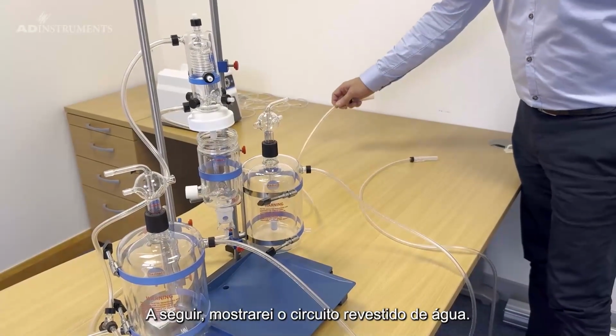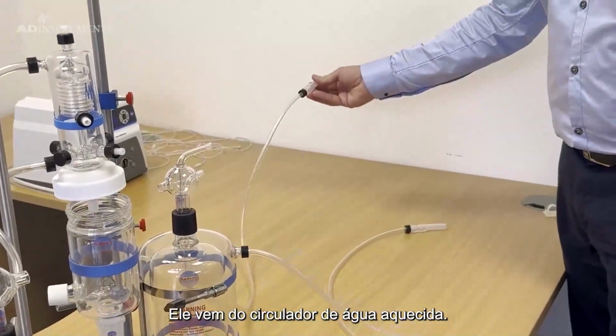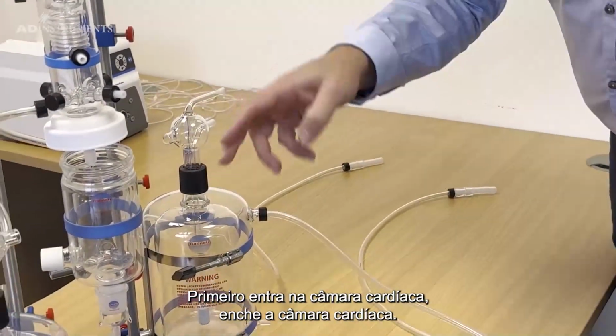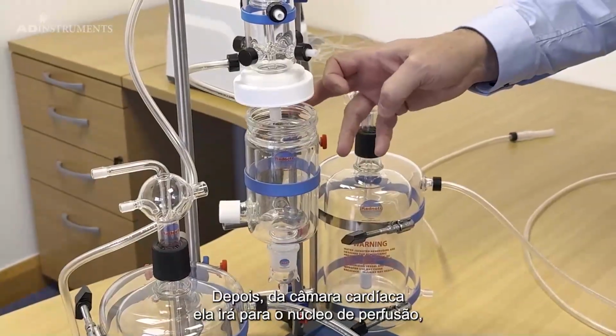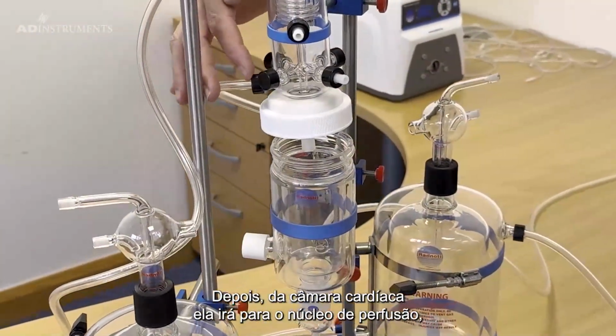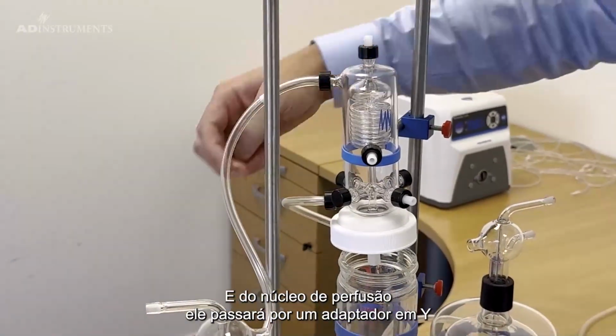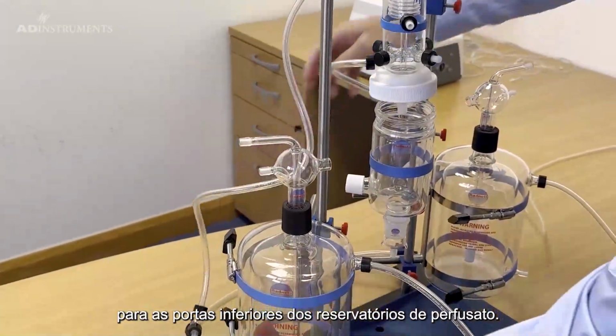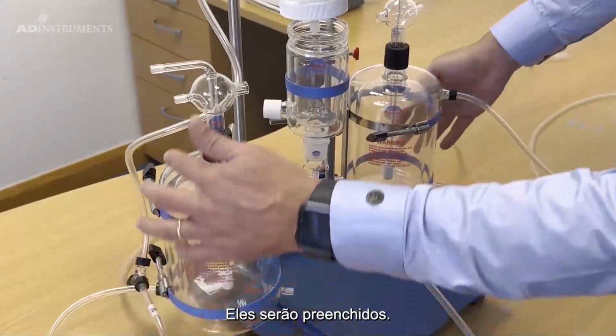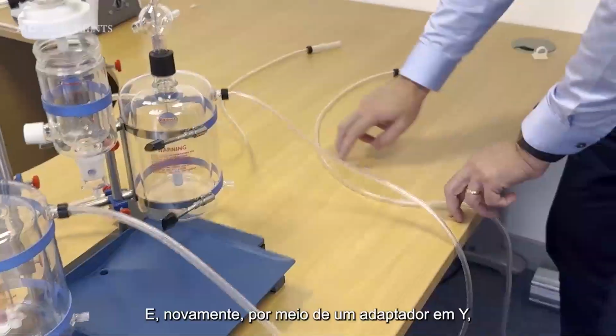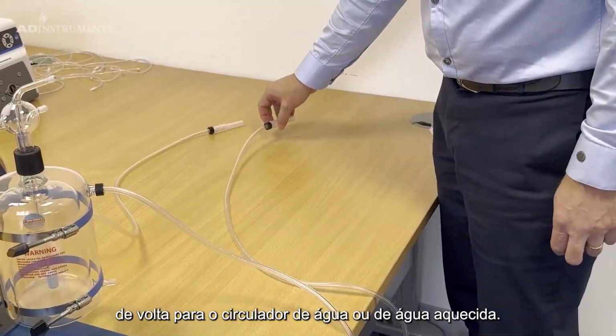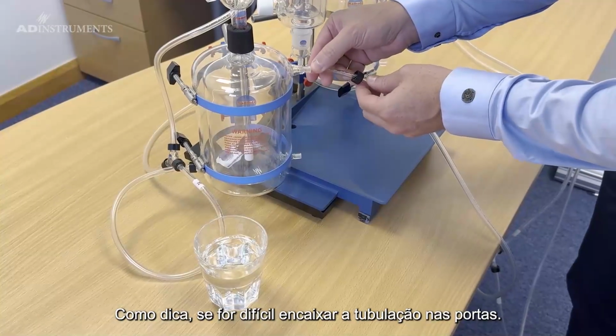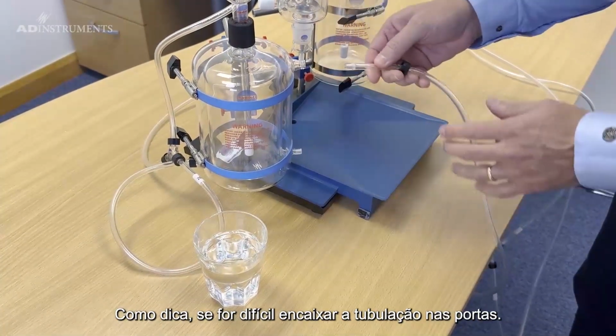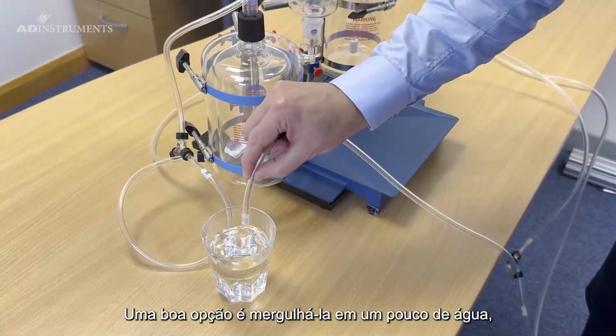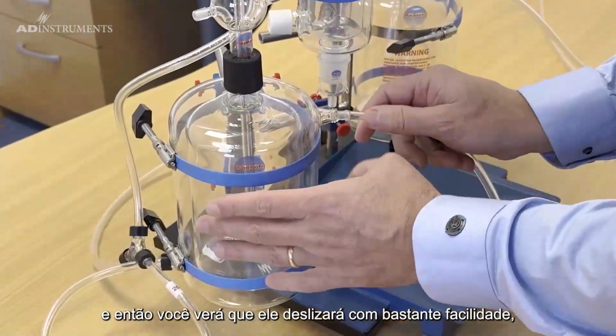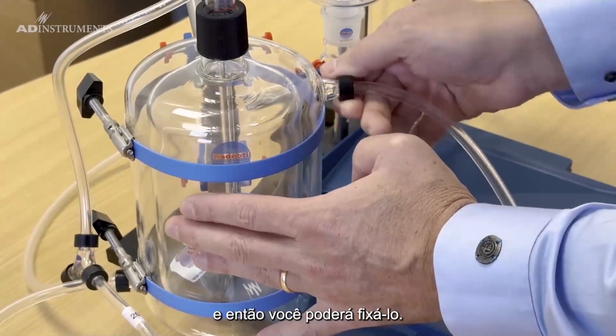Next, I'll show the water jacketed circuit. So it comes from the heated water circulator. First goes into the heart chamber, fills up the heart chamber. Then from the heart chamber, it will go to the perfusion core, fill up the perfusion core. And from the perfusion core, it will go through a Y adapter to the bottom ports of the perfusate reservoirs. These will fill up, and then again through a Y adapter back to the heated water circulator. As a tip, if it is difficult to fit the tubing to the ports, a good little tip is to just dip it in some water, and then you'll see it'll slide in quite easily, and then you can fasten.